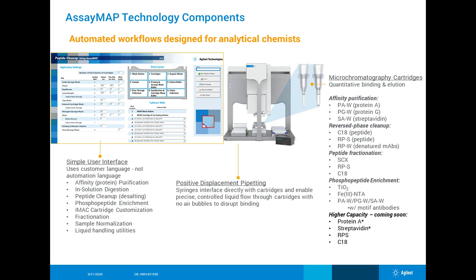The AssayMap Bravo head is built a little bit differently so that it can work with these microchromatography cartridges. It is a positive displacement pipettor with 96 syringes all at once. They work directly with the cartridges and enable precise, controlled liquid flow through the cartridges so you don't have any air bubbles or any disruption of the binding — you can control the flow rate. Think of the head and syringes like the pump and the cartridges like your column, which is why we consider this microchromatography technology.